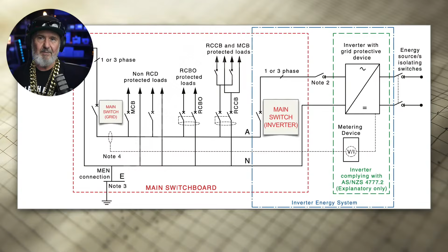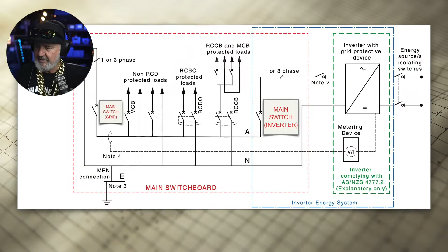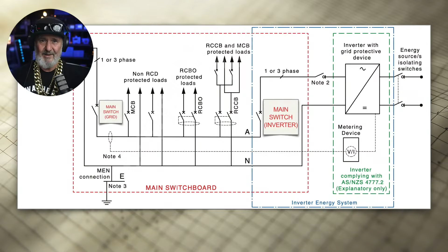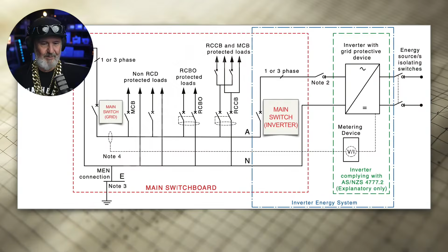Jeff just said they're replacing the second version too, but my guess is the first version was the one causing issues. Yep, proper crimping on ferrules. Okay, Jeff, that's interesting. I didn't realise there were actually two versions which were using ferrules, a push fit and a screw fit. I didn't know that, so thanks, Jeff. Wow, you've done a lot, 50 installs. Does that mean you've got to go back to 50 of them and change them? Wow, right at the busiest time of the year, when everyone's saying, can I get my new SIG system installed just before the battery rebate reduces on the 1st of January. Yeah, I feel for you. A crazy time. That's what rebates do.